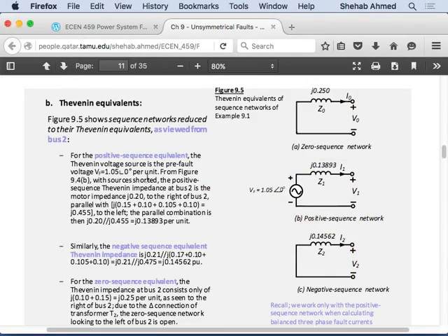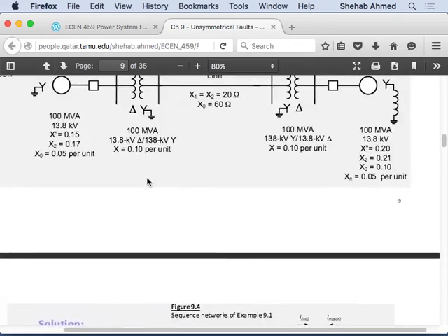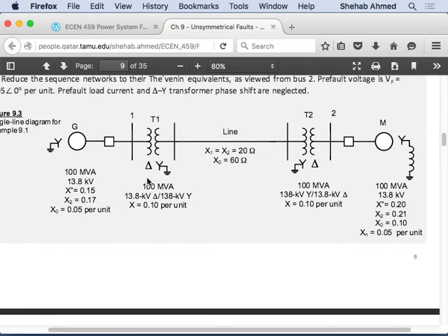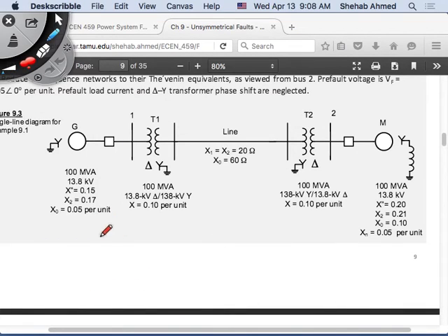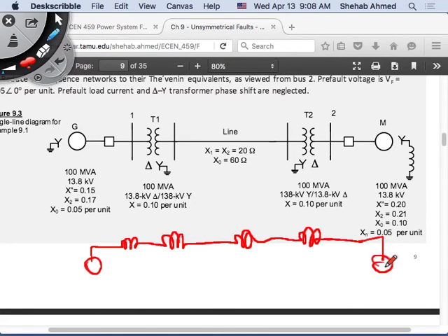This will be the fault current at this location for a three-phase fault, right? For me, it's basically the impedance diagram thing we did before. You have your impedance diagram and put a short circuit at a certain location. If you would like to see what the voltage source is, what the value of voltage. So for your impedance diagram, we had the generator, impedance, impedance, impedance, impedance, and then motor, impedance.